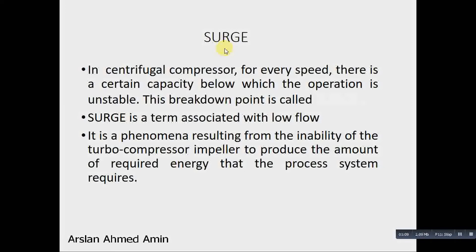Now we will discuss a very important property, the surge. At a specific capacity, for every speed, there is a certain capacity below which the operation is unstable. This breakdown point is called surge. Surge is a term associated with low flow. So for a certain RPM, the minimum flow point is the surging point.